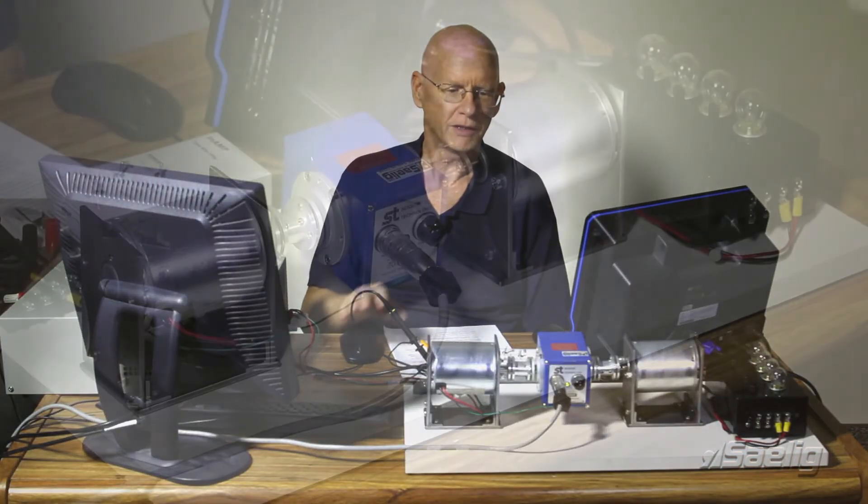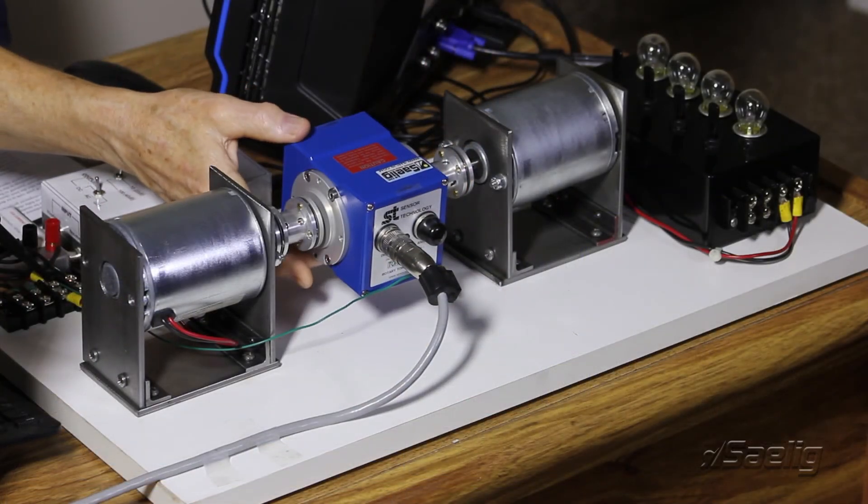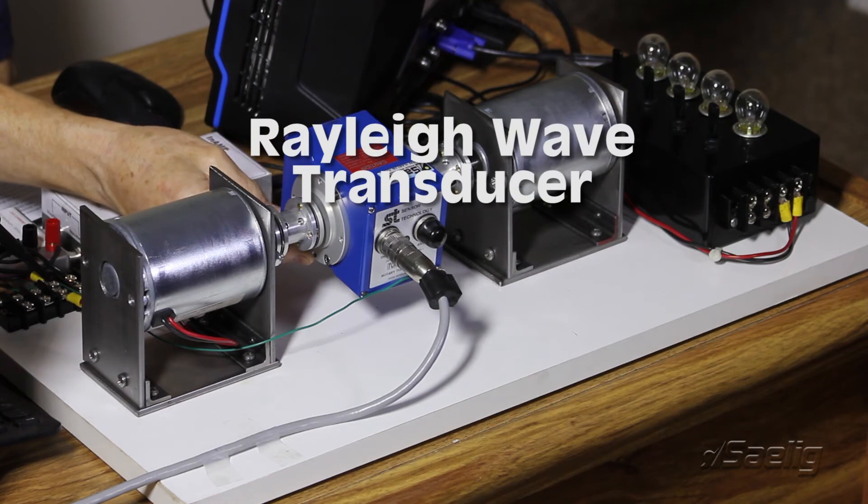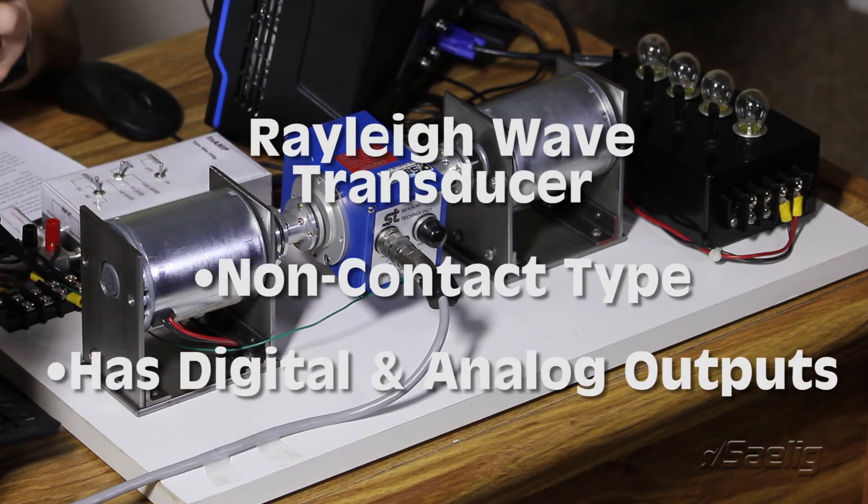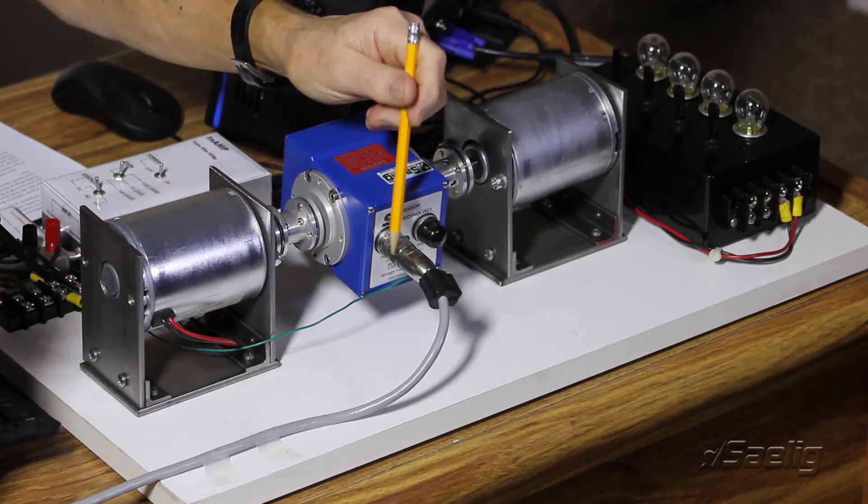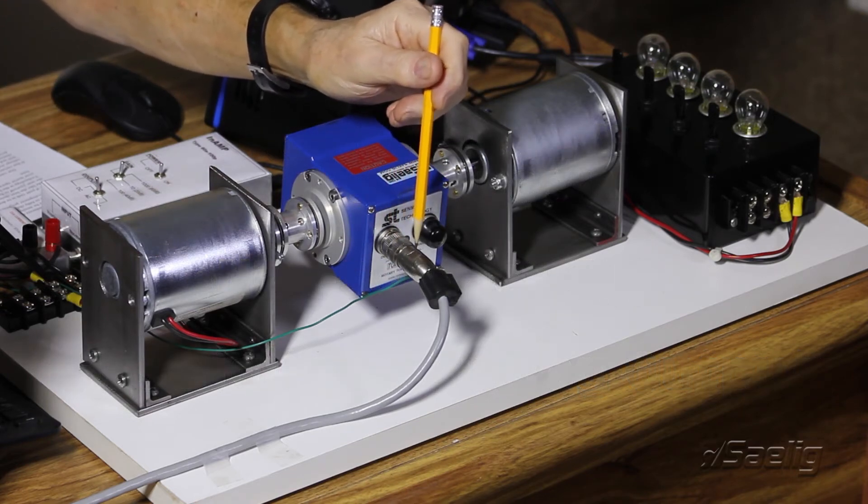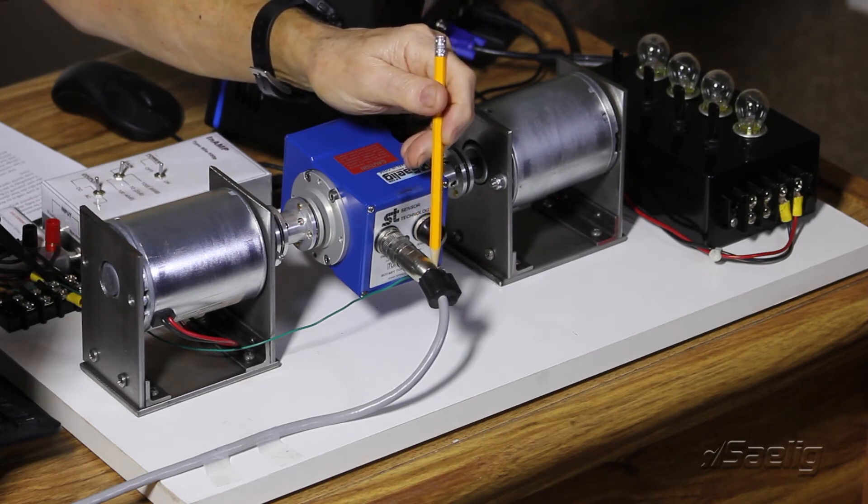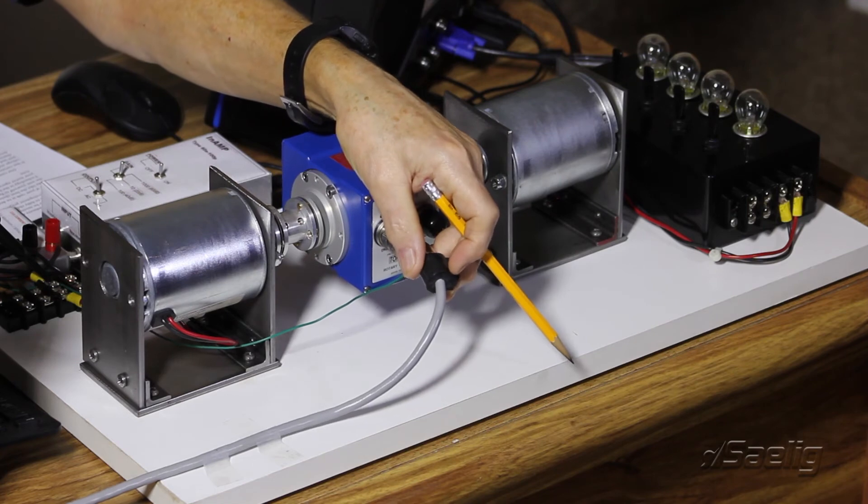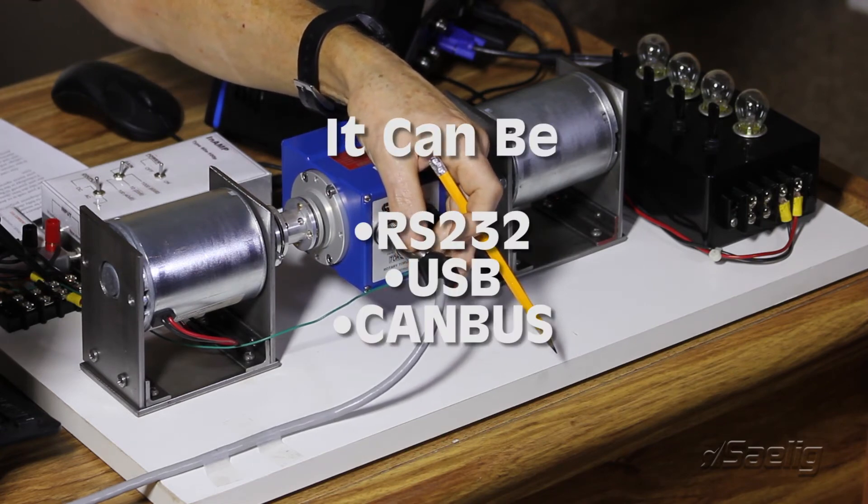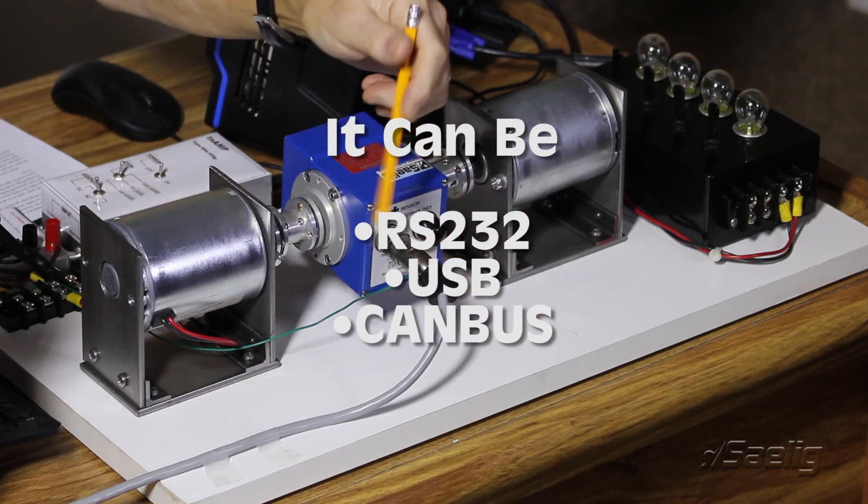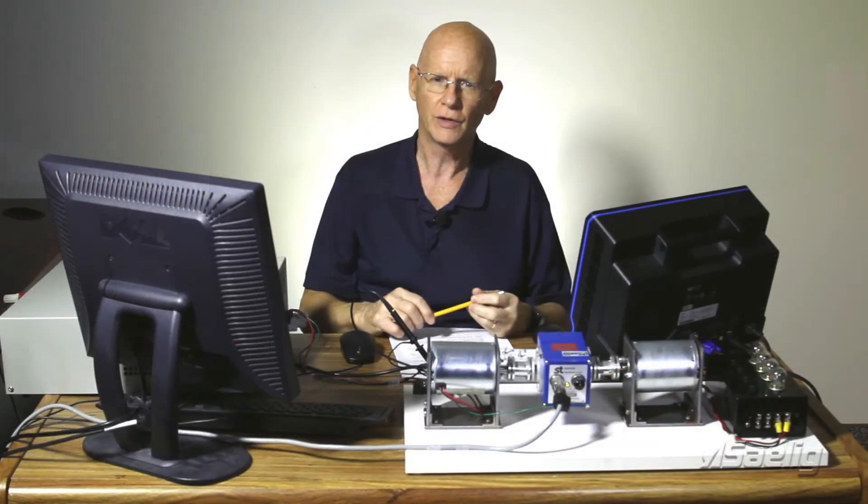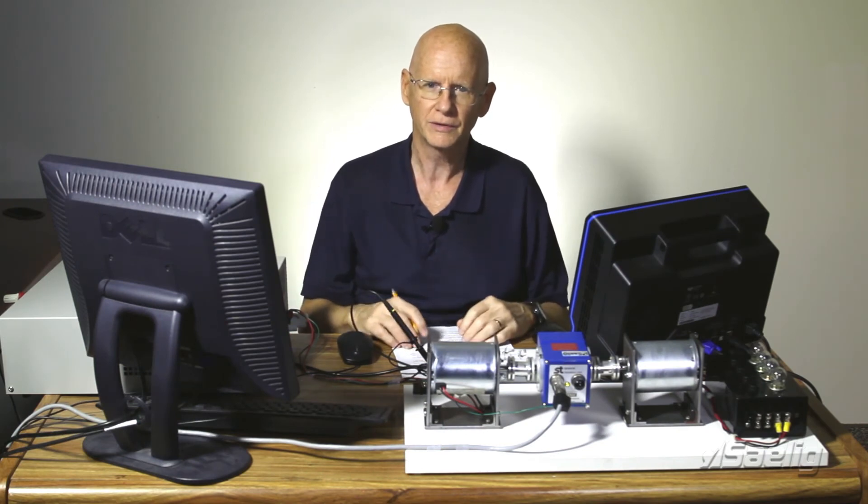First of all, let me just mention that the torque transducer itself is a Rayleigh wave transducer and it's a non-contact type and it has both digital and analog outputs available to it. And in this case here in our test system, we're using just the digital output, which you can get to be any number of data presentation types. It can be RS232, USB, or CAN bus. And in the case of this transducer, this one happens to be connected with USB. So it just connects right into the computer. It's very easy to use.